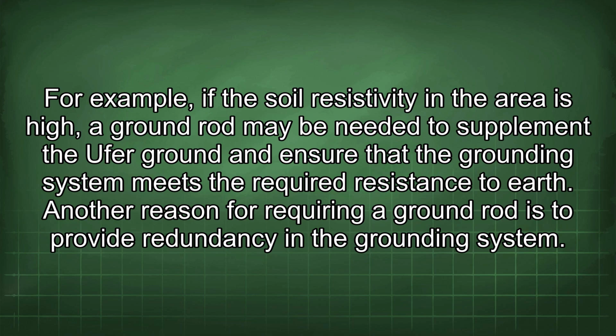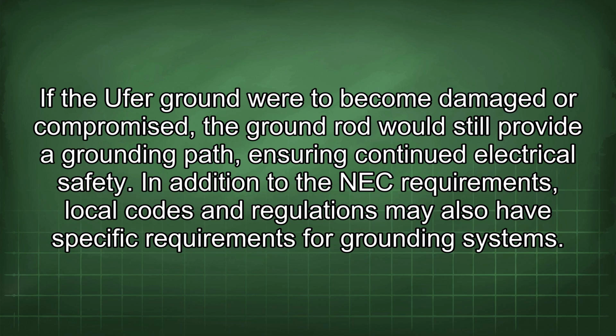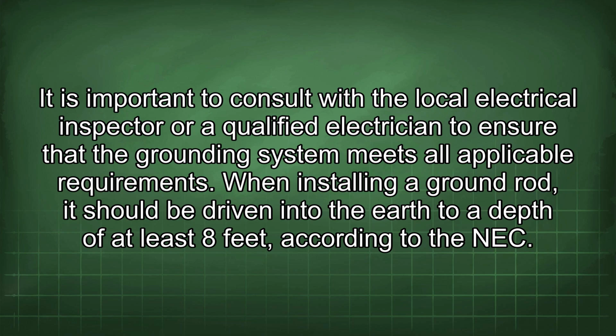Another reason for requiring a ground rod is to provide redundancy in the grounding system. If the Ufer ground were to become damaged or compromised, the ground rod would still provide a grounding path, ensuring continued electrical safety. In addition to the NEC requirements, local codes and regulations may also have specific requirements for grounding systems. It is important to consult with the local electrical inspector or a qualified electrician to ensure that the grounding system meets all applicable requirements.